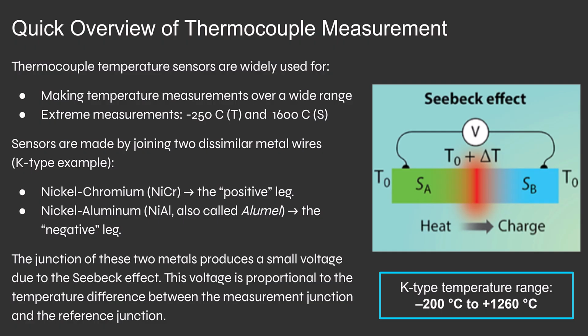There are different types of thermocouple sensors out there: T-type, S-type, J-type, K-type. You can see I provided an example for K-type. You can see the 2 metals that are used—where they combine, that junction is where we apply our temperature measurement, or use them as a sensor to measure temperature. The benefit of them, as I mentioned, is they cover a large temperature range compared to most types of temperature sensors. Their disadvantage, though, is they don't have very high accuracy. Taking into account all the error effects, they typically only give you about plus or minus 2 degrees C, or maybe at best plus or minus 1 degree C.